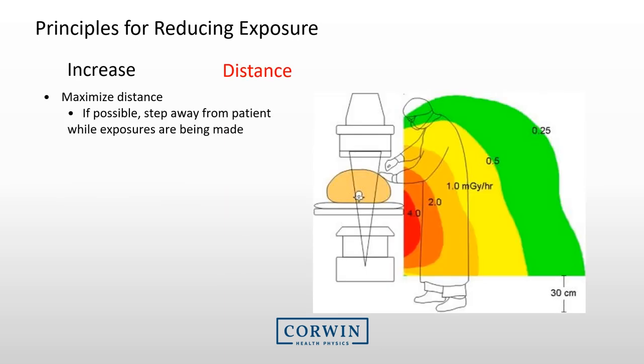Another easy way to reduce your radiation exposure is to increase your distance from the radiation source. The x-ray tube is on the bottom of the patient and the imaging surface is above. When the x-ray tube fires, radiation scatters in all directions in an inverse square pattern. If you stand just a few feet back, radiation exposure levels drop off significantly. We encourage you to stand a few feet back whenever possible, as long as you can still provide necessary patient care.